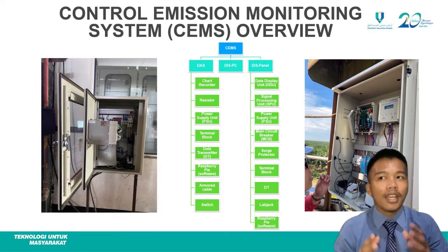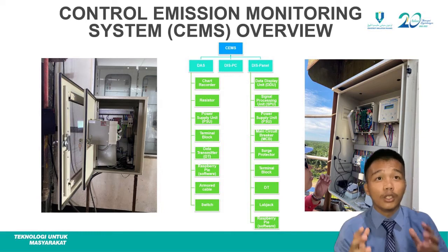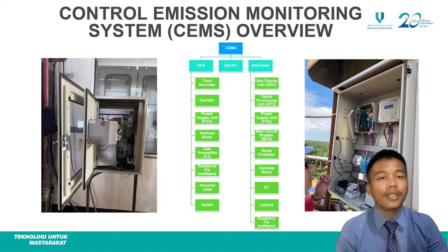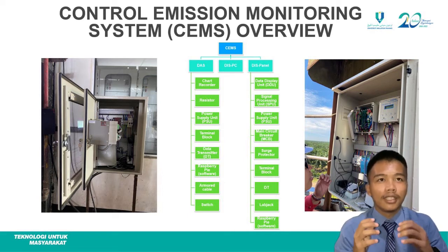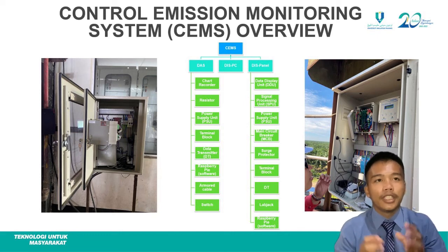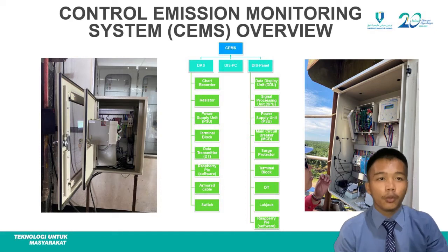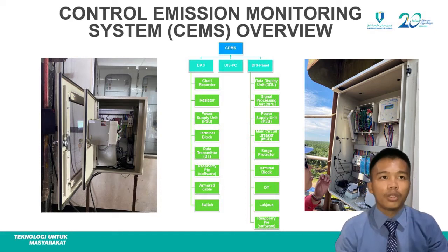And as for the DIS panel, it has a data display unit, also known as DDU, signal processing unit SPU, power supply unit PSU, main circuit breaker MCB, surge protector, terminal block DT, LabJack, and Raspberry Pi as its software. Okay, for the DIS panel, the DDU will display the signal that is transmitted from the sensor, and the SPU, signal processing unit, will process the signal to be displayed at the DDU. For the PSU, it has two PSUs. The first one supplies power to the DDU and SPU, and the next one supplies power to the compressor.